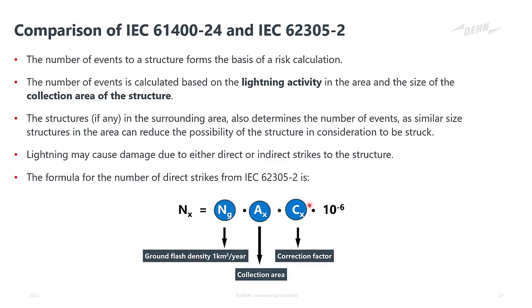Now, this is the formula for calculating the number of direct strikes from IEC 62305 part 2. What 61400 does is it changes the lightning activity in the area. I will explain why in the next slide. And the correction factor for a wind turbine is very different from that for a typical structure. Typically, these structures are very tall. They are installed in areas where there are high elevations. They are subject to winter lightning, and that changes things. So if we increase the correction factor and we increase the lightning flash density, or the lightning activity in the area, the number of strikes will then also obviously be increased. And that's where 61400-24 has some of the biggest differences as opposed to 62305 part 2.